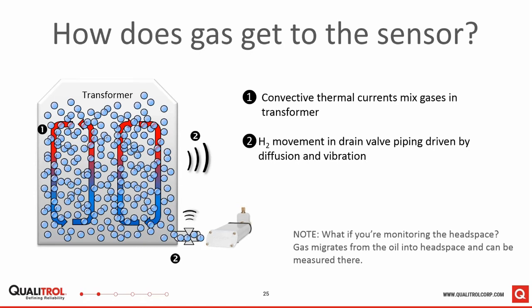But for transformer faults in general, they take weeks or months or years to develop. So taking hours to detect the production of gas is still extremely rapid. And in any case, the alternative, taking the sample to the laboratory, is still at the mercy of that oil needing to circulate, and you only get a snapshot from the lab. And of course, if you use the headspace application of this sensor, the gas naturally will distribute itself between the oil and the gas phase or the headspace phase of the transformer.